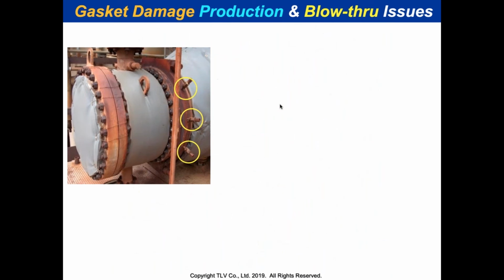It's easy to see where people are having problems. This is what I call the double whammy right here. So I come into a reboiler and I take a look and I see, well, look what's happening there with that collar.